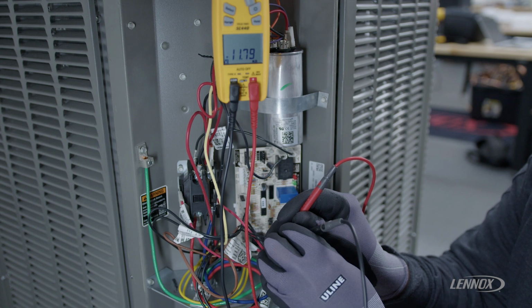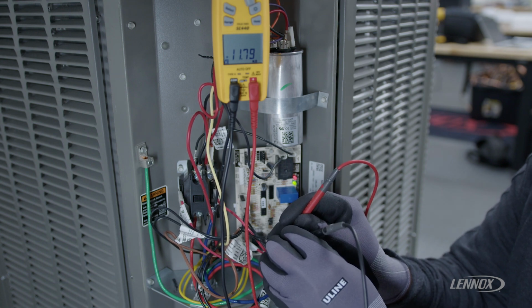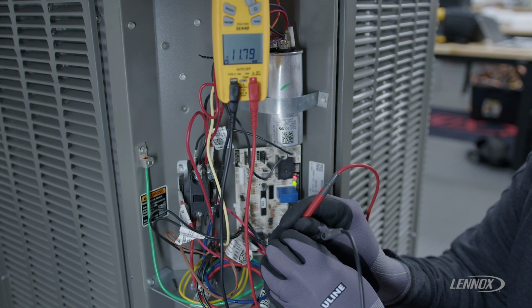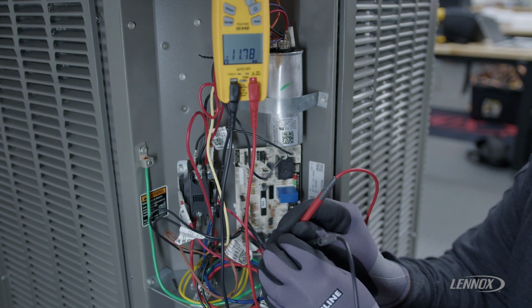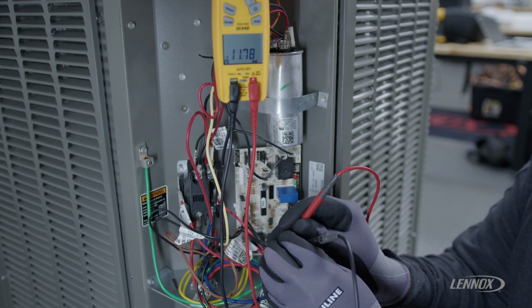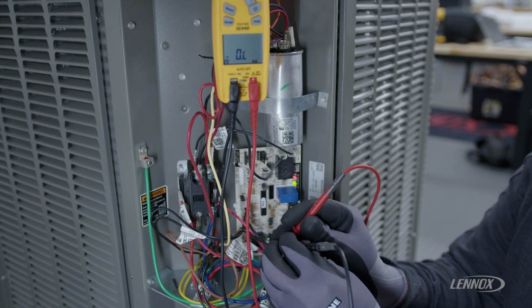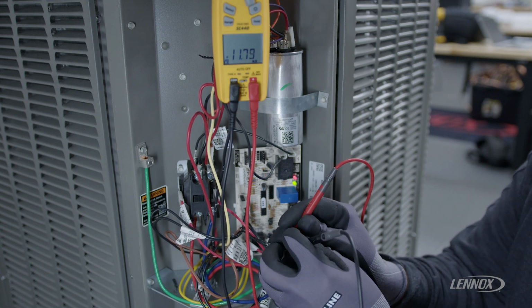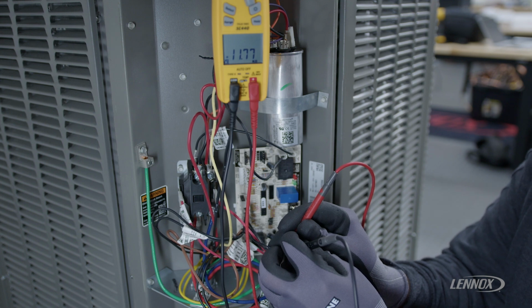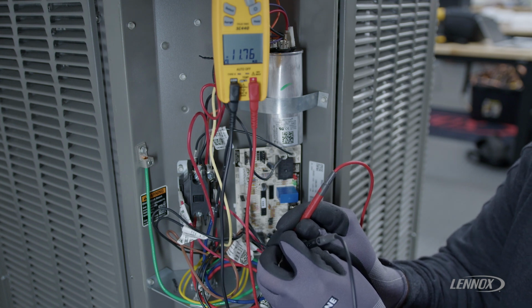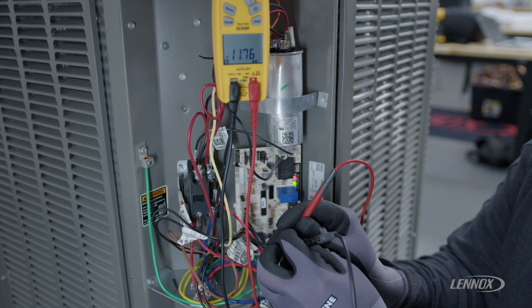This reading tells us the resistive value of that sensor, which is a 10K resistive sensor. Looking at the chart, 11,000 ohms tells us we're at about 70 to 74 degrees. This is how you'll test the integrity of the ambient sensor. If it's within range, the sensor is good. If it's out of range, you'll have to change the sensor.